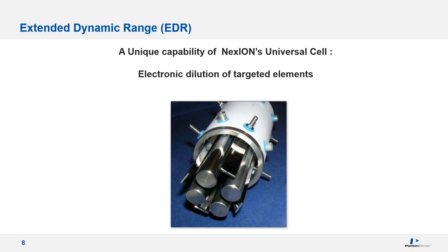Another great feature of our ICP-MS systems is the capability of the universal cell to utilize EDR, or extended dynamic range. This capability enables the analyst to use the quadrupole inside the universal cell to detune sensitivity on specific high-concentration elements so that they can be analyzed together with very low concentration elements, extending the dynamic range of the detector to over nine orders of magnitude. EDR can be included in a multi-mode method with either an Elan DRC or a NexION ICP-MS system. Once you know your sample matrices, this can be fine-tuned in your method and can offer a dramatic boost in productivity.